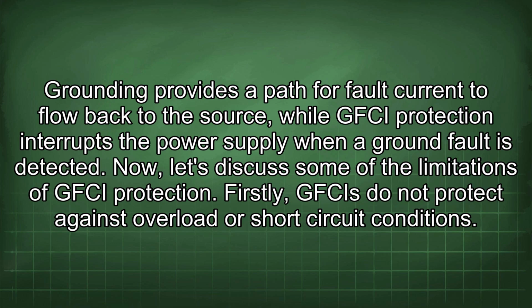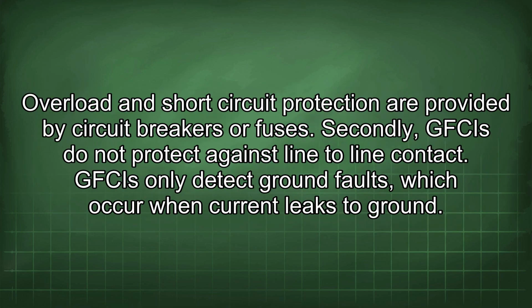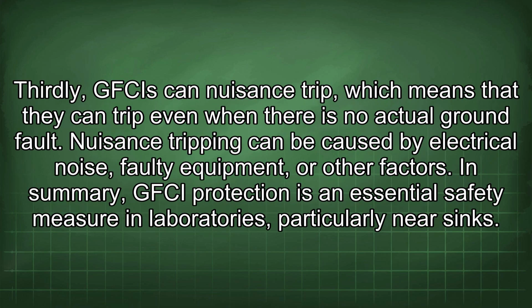Now, let's discuss some of the limitations of GFCI protection. Firstly, GFCIs do not protect against overload or short-circuit conditions. Overload and short-circuit protection are provided by circuit breakers or fuses. Secondly, GFCIs do not protect against line-to-line contact. GFCIs only detect ground faults, which occur when current leaks to ground. Thirdly, GFCIs can nuisance trip, which means that they can trip even when there is no actual ground fault. Nuisance tripping can be caused by electrical noise, faulty equipment, or other factors.